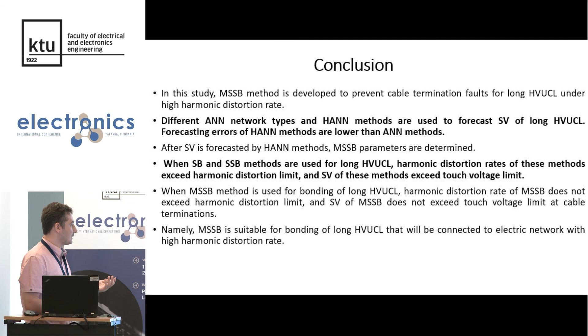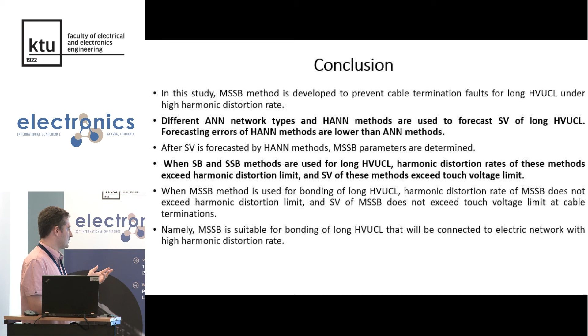When the MSSB method is used for bonding of long high voltage underground cable lines, the harmonic distortion rate of MSSB does not exceed the harmonic distortion limit, and SV of MSSB does not exceed the touch voltage limit at cable termination. Namely, MSSB is suitable for bonding of long high voltage underground cable lines that will be connected to the electric network with high harmonic distortion rate.